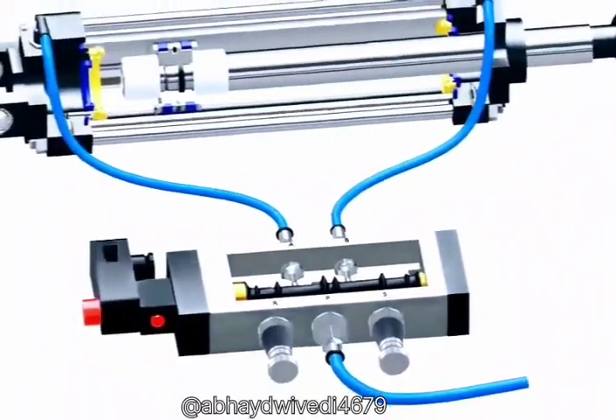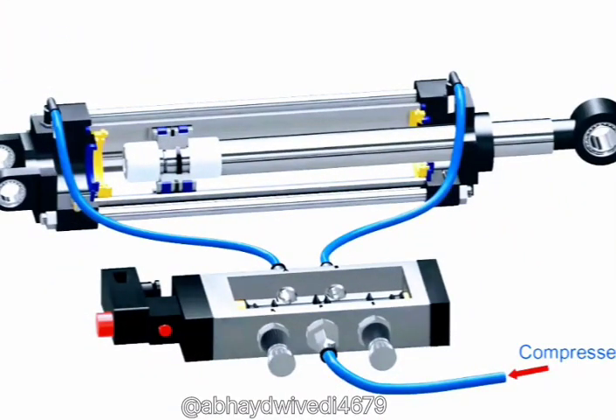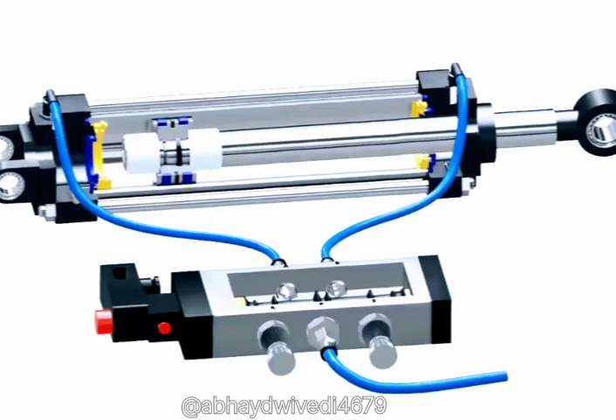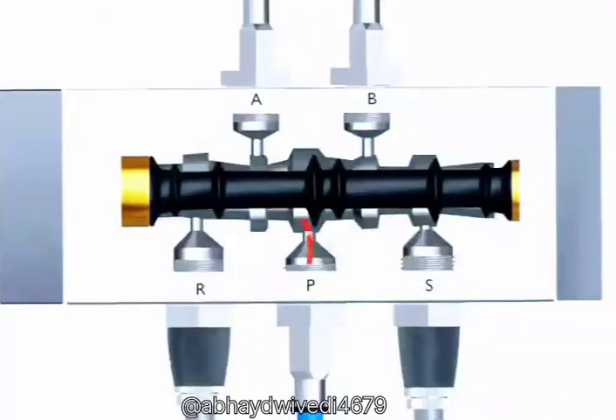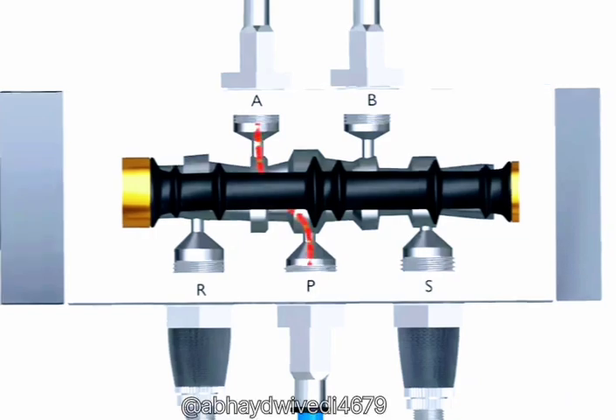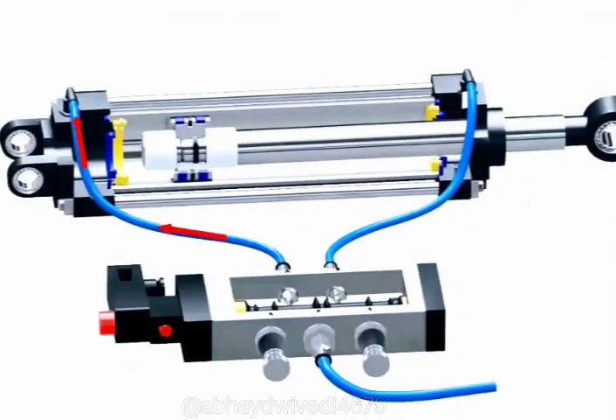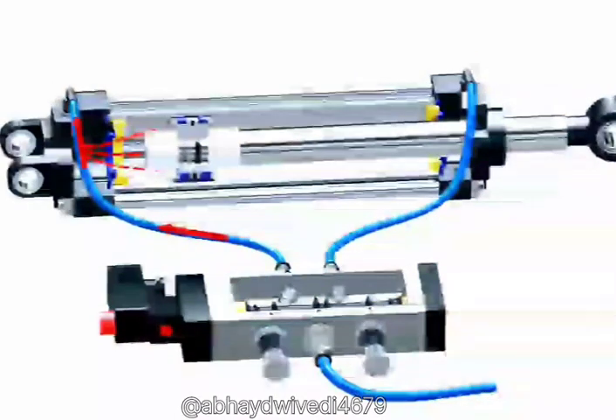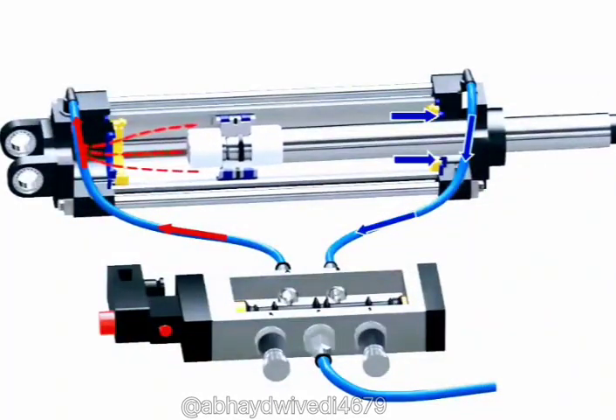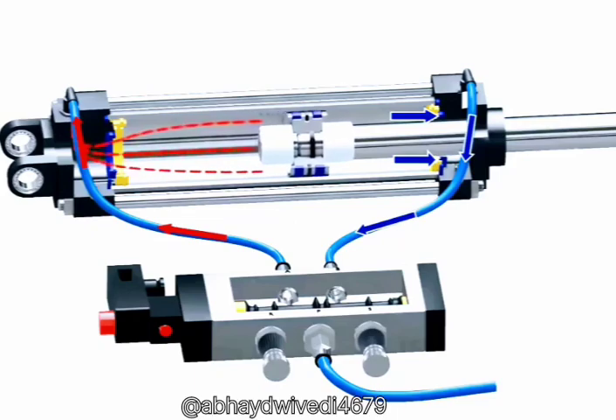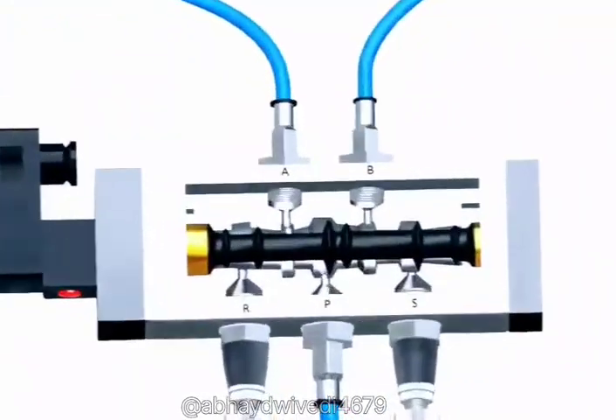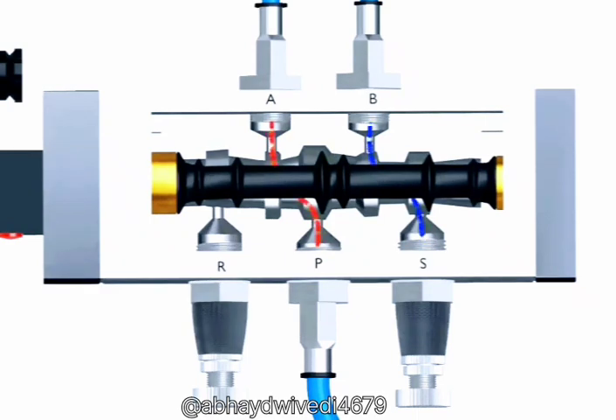Now let's understand how a pneumatic cylinder works. Compressed air is supplied through inlet port P of the valve. The valve directs air to a particular direction, which we can observe in the animation. In this case, the air is directed to port A. This high-pressure gas is then transferred to the cap end of the cylinder through the pneumatic hose, creating high pressure that pushes the piston towards the head end. This also pushes gas from the head end, and this exhaust gas travels through the other hose back to the valve. The valve directs this gas towards port S and allows it to escape through a pneumatic muffler, which helps to reduce any noise produced during exhaust.